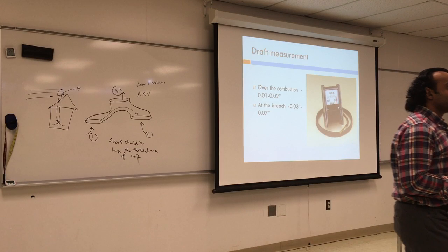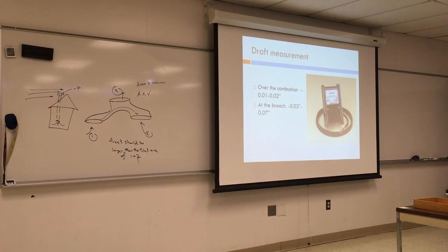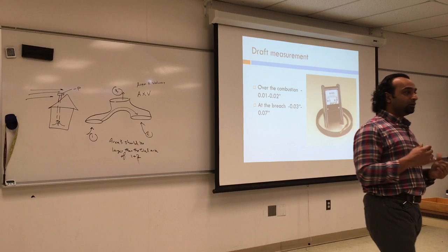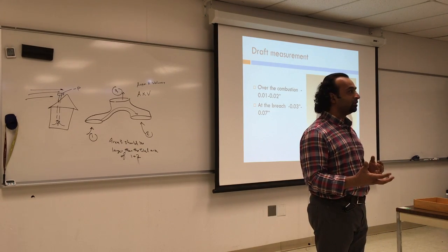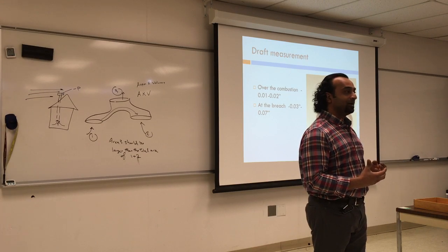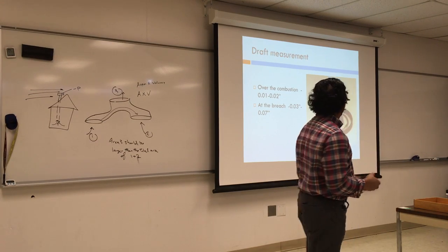So again, for smoke test and for temperature, you do not go inside the chamber. The only thing you put inside the chamber is what? The draft. So please remember that. I'm going to keep repeating it because it's very important to know how to do combustion testing. Combustion testing is very important, and you can do it either manually using a mechanical kit or electronically, and sometimes it's really good to verify using both.